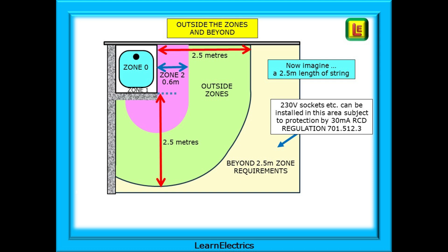Exam questions will try and catch you out by suggesting this is Zone 3 — it's not, it's called outside the zones. It extends from where Zone 2 ends to a distance of 2.5 metres from the edge of Zone 1, effectively 1.9 metres in width if you knock off the Zone 2 width. Imagine a 2.5 metre length of string: everywhere the string can reach beyond Zone 2 and still touch the shower basin is outside the zones and has reduced requirements. But we can install 230 volt sockets in this area, protected by a 30mA RCD.